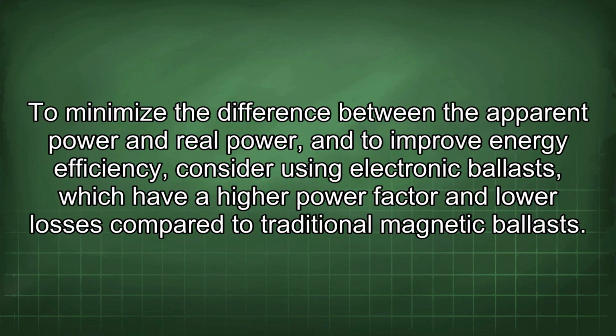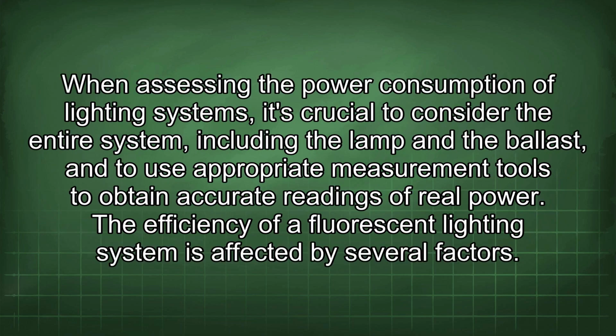To minimize the difference between the apparent power and real power, and to improve energy efficiency, consider using electronic ballasts, which have a higher power factor and lower losses compared to traditional magnetic ballasts. When assessing the power consumption of lighting systems, it's crucial to consider the entire system, including the lamp and the ballast, and to use appropriate measurement tools to obtain accurate readings of real power. The efficiency of a fluorescent lighting system is affected by several factors.